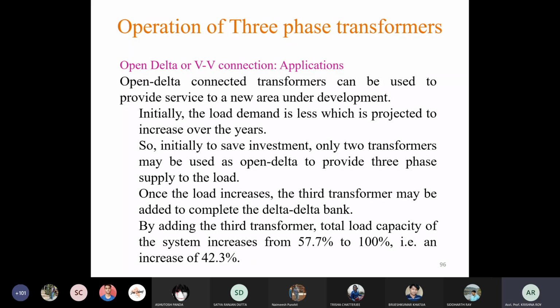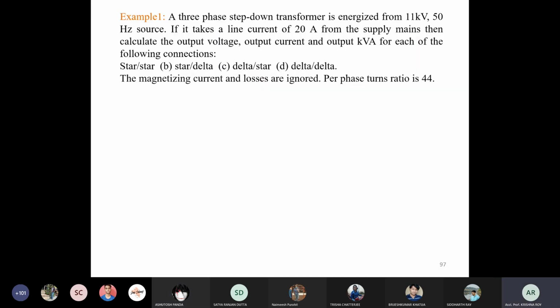One advantage is that in an accidental case, we can remove the faulty transformer and still operate with the existing open delta connected system. But another important advantage is that we can increase the system capacity by installing the third transformer, increasing the capacity to 100%, that is an increase of 42.3%. Clear? Okay, that's all about the 3-phase transformer.